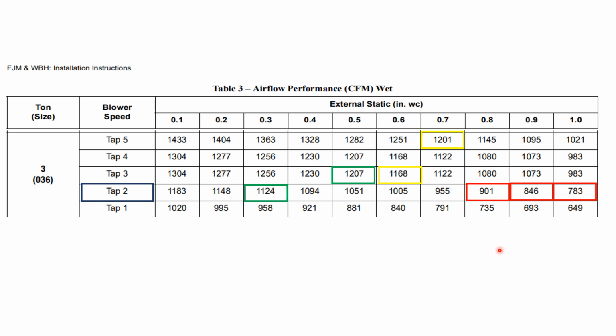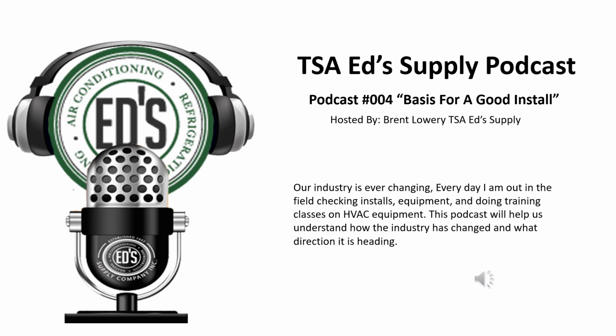So in this situation, we could take this speed tap, move it to speed tap 3, and make sure we're at 0.5 or less, we're safe with ICP, and we're making 1207 CFMs. Then I can go back and dial some of those rooms down or add a little bit more if I have a flow hood or any device like that, and we'll talk about that in other podcasts as well. But that's the main thing I wanted to talk about in this podcast.